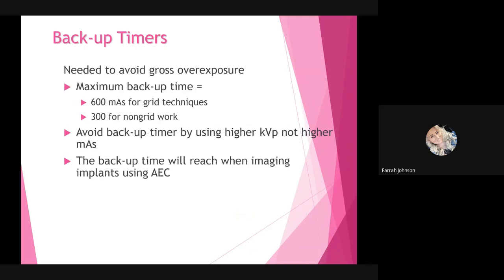Whenever you're dealing with AEC, we have backup timers, and backup timers are needed to avoid gross overexposure. Note that with mammography machines, the maximum backup time required is going to be 600 mAs for grid techniques and 300 for non-grid work. You want to avoid the backup timer by using higher kVp, not higher mAs, because otherwise your patient radiation dose will be significantly higher. The backup timer will be reached when imaging implants using AEC. So typically you'll use a manual technique if you're imaging patients with breast implants, because those implants are so dense that the backup time will automatically max out when placed over the AEC chamber.